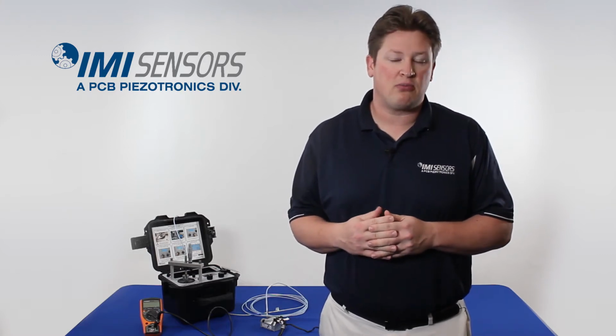In this demonstration, I'm going to show you how to use our portable vibration calibrator with a pre-programmed proximity probe test to create a calibration certificate for proximity probes dynamically in Microsoft Excel. Three clicks of the mouse, no software other than Microsoft Excel is required.